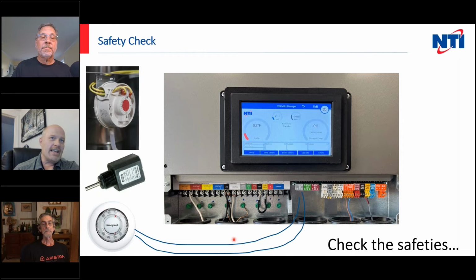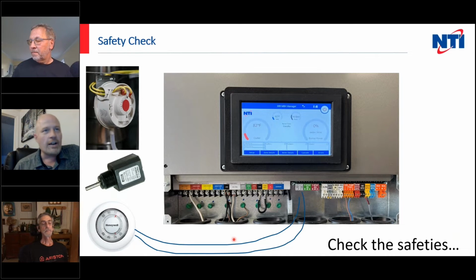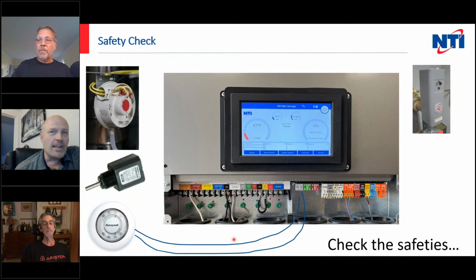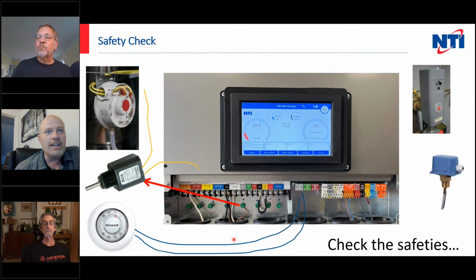We're then going to look at any internal safeties. I've picked sort of representative safeties for this product. So there's a low water cutoff, there's a blocked condensate switch, and basically the power for the gas valve actually passes through those devices. And then we have an auxiliary limit, and these are things that you would wire external to the boiler, and they're going to go back to the low voltage terminal strip. So roughly speaking, your wires are going to come from the control and go back to the control for the internal limits, provided we have continuity through these.